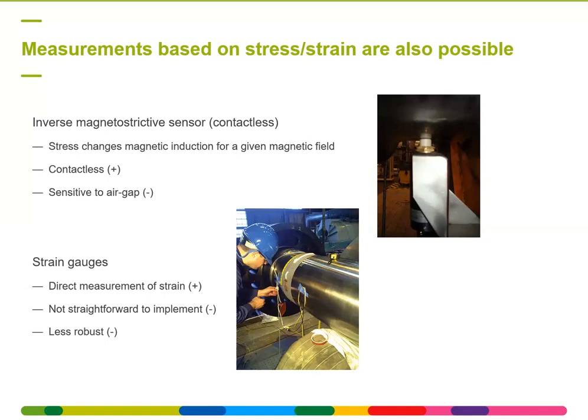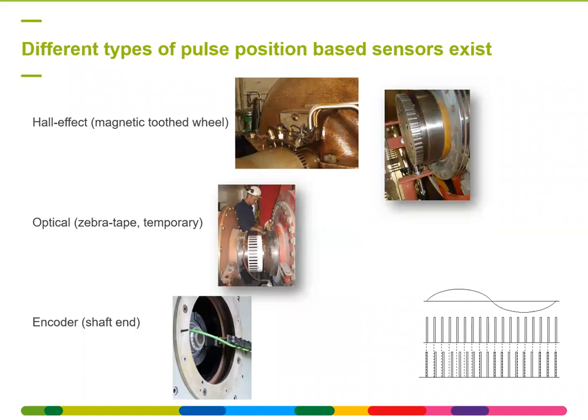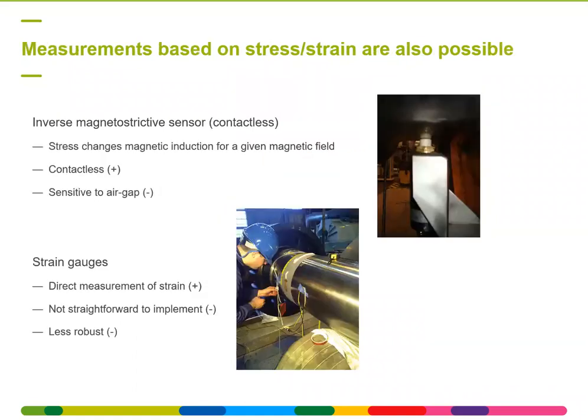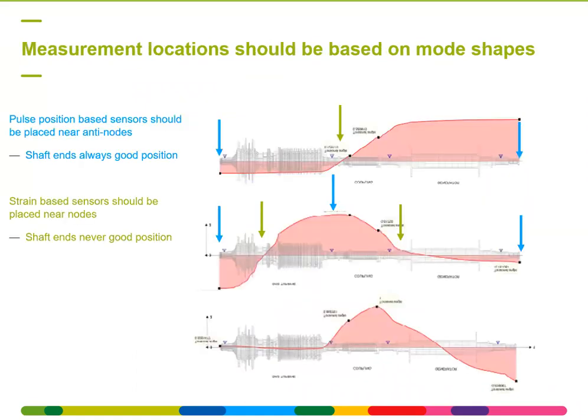In general, the most standard probe used for torsional vibrations is the Hall effect one. These are also the standard ones used for speed measurements, and you can use these existing ones in a torsional vibration measurement campaign if they're well positioned. And this is shown on the next plot.